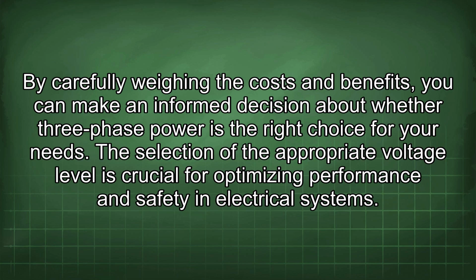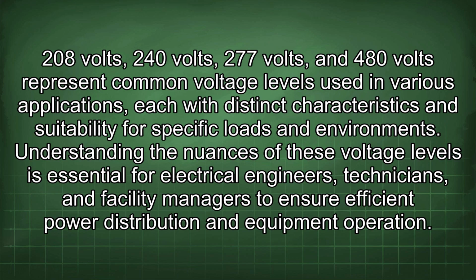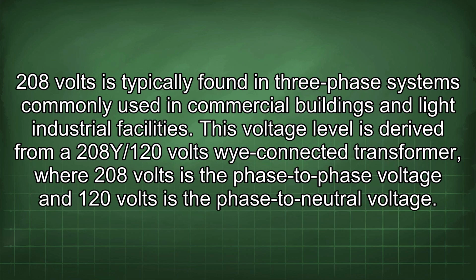choice for your needs. The selection of the appropriate voltage level is crucial for optimizing performance and safety in electrical systems. 208 volts, 240 volts, 277 volts, and 480 volts represent common voltage levels used in various applications, each with distinct characteristics and suitability for specific loads and environments. Understanding the nuances of these voltage levels is essential for electrical engineers, technicians, and facility managers to ensure efficient power distribution and equipment operation. 208 volts is typically found in three-phase systems commonly used in commercial buildings and light industrial facilities. This voltage level is derived from a 208Y/120 volts Y-connected transformer, where 208 volts is the phase-to-phase voltage and 120 volts is the phase-to-neutral voltage.